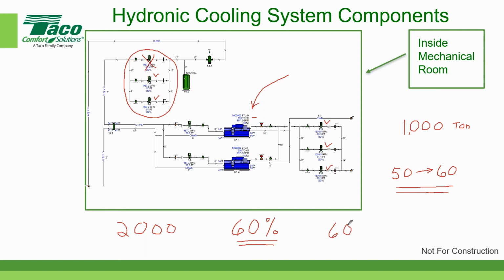Well, you may want a system to have more turndown ratio, but you can't do it with variable primary flow. But you can with primary secondary, because you can maintain constant flow through your chillers at 100%, and then you could vary your secondary pumps to almost anything you want to meet the demands of the system. So primary variable flow has its benefits in energy, but it's not quite as flexible as a primary secondary system. There are some comments that it's pretty finicky and maybe over the head of some typical maintenance staffs, and maybe the controls for some folks may be difficult.